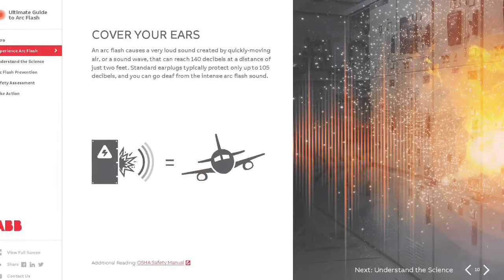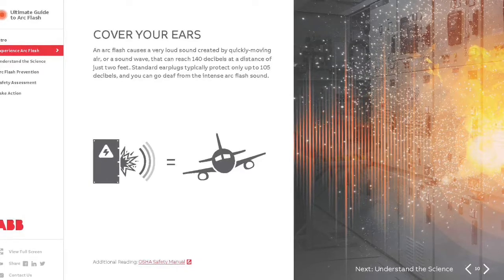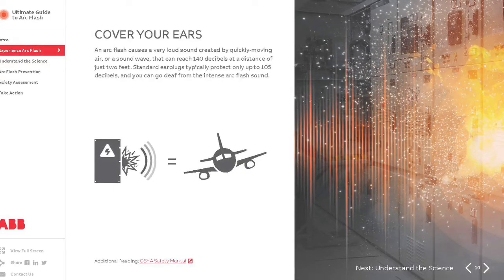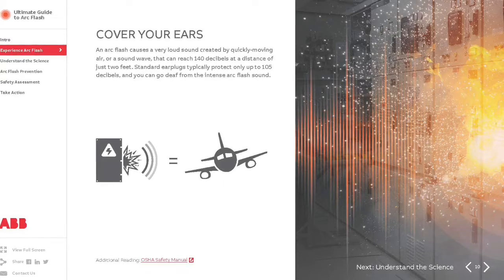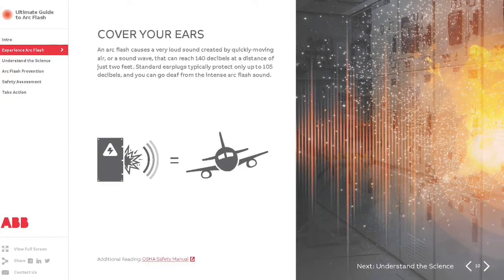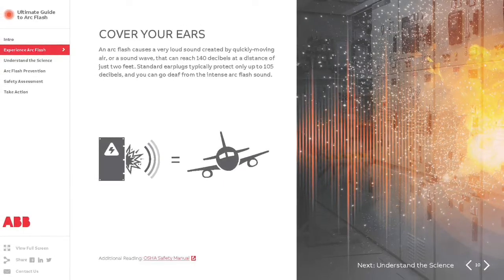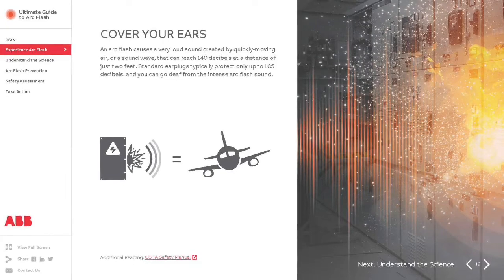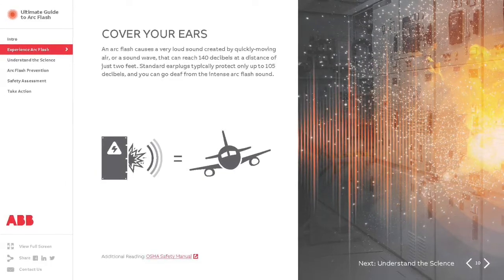An arc flash causes a very loud sound by quickly moving air, or a sound wave that can reach 140 decibels at a distance of just 2 feet. Standard earplugs typically protect only up to 105 decibels, and you can go deaf from the intense arc flash sound.